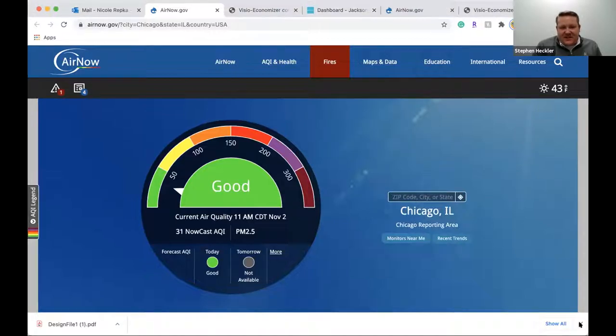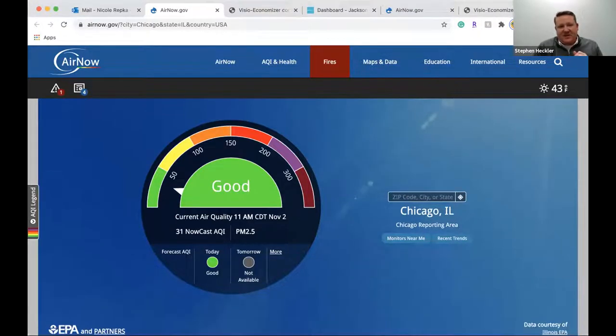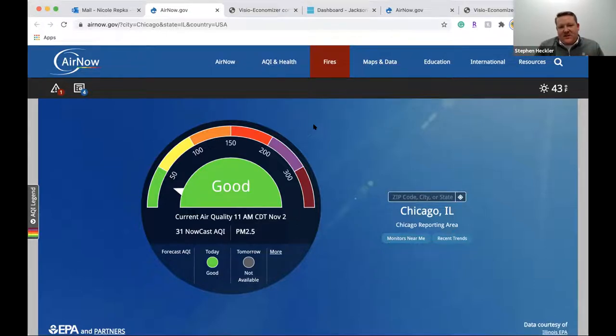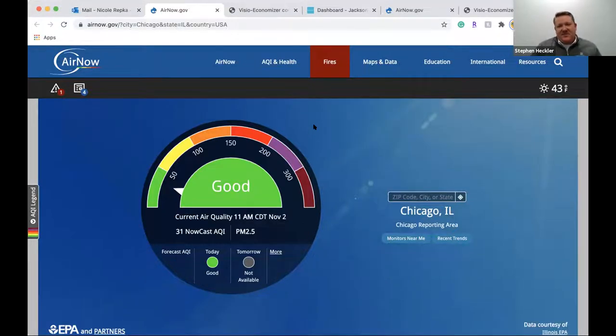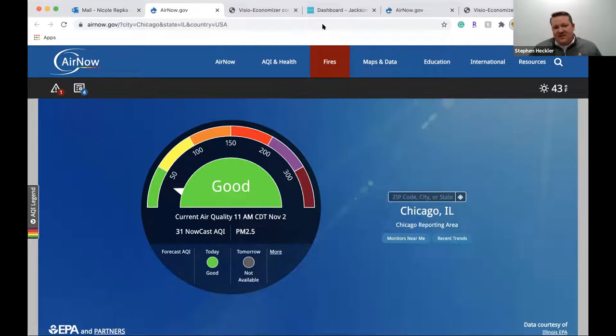There's a site called airnow.gov where you can type in any locality and see what the outside air quality is that day. When we talk about treating indoor air, one of the biggest recommendations is to bring in outside air — which is great, unless the outside air is worse than the inside air. Much like a weather service in a typical building automation system, we can use a data transfer module to connect to airnow.gov, check the outside air quality, and decide whether to let in outside air or treat the air inside the building using UV lights in the duct, better air filters, or ionization.